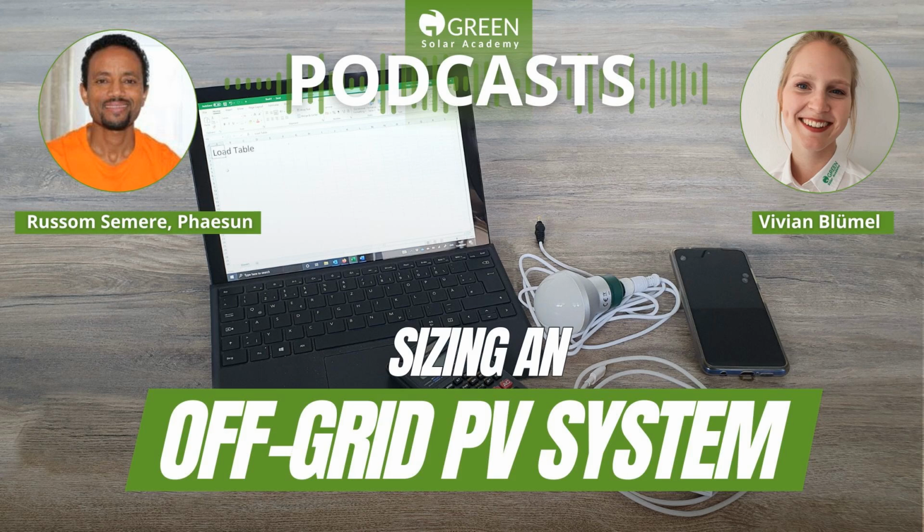And the charge controller size also, it is connected to the module and to the DC loads and to the battery. So it must have the capacity to take all the current which is coming from the solar module, and it must be able to support all the DC loads which are going to the loads. So the charge controller should be able to support the energy that's coming from the module and the energy which is going to the DC loads.